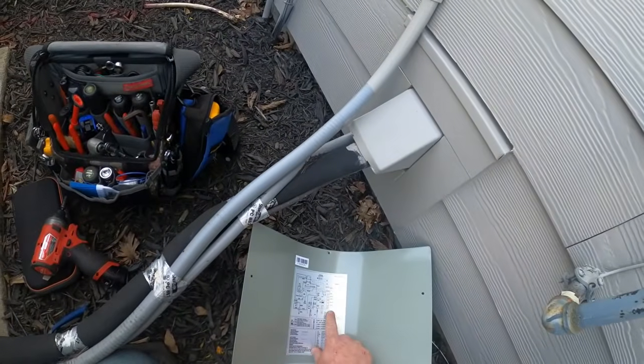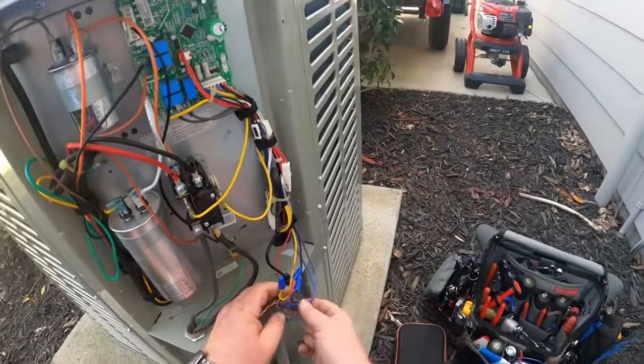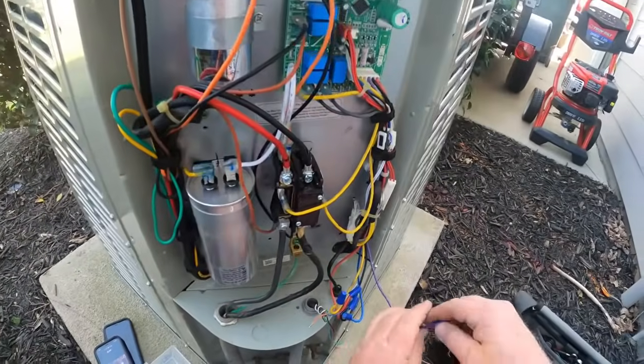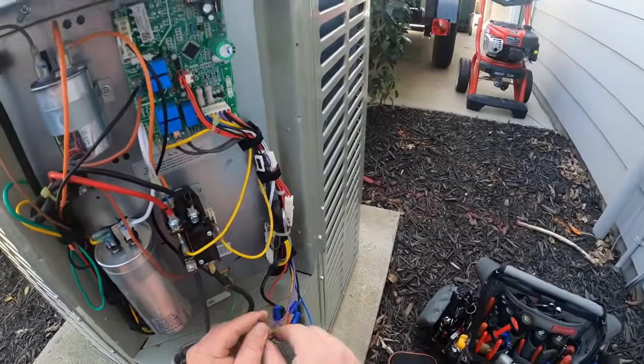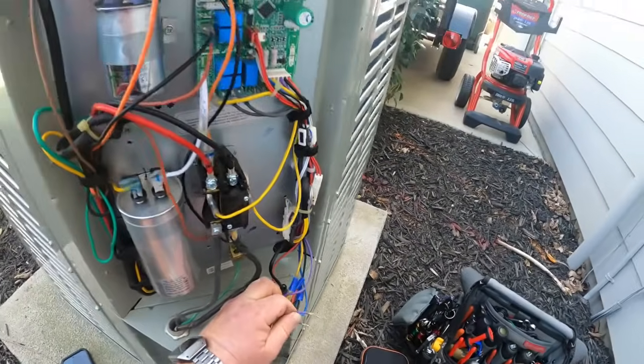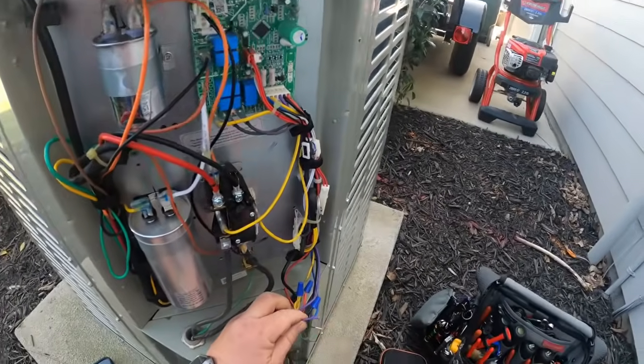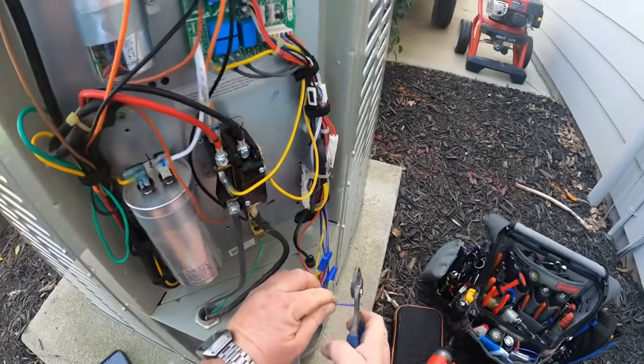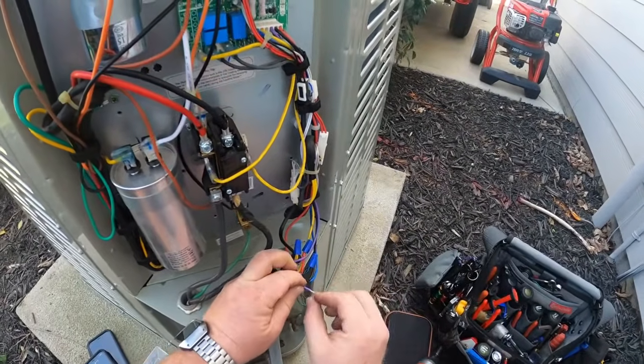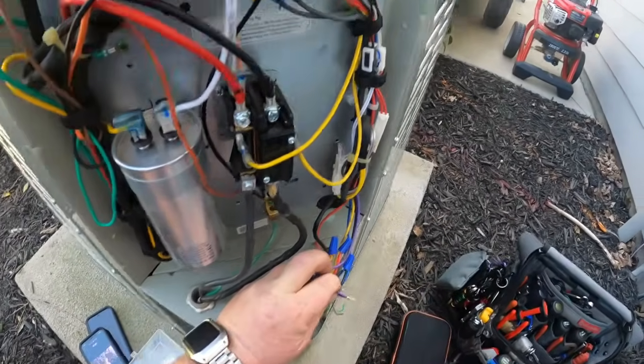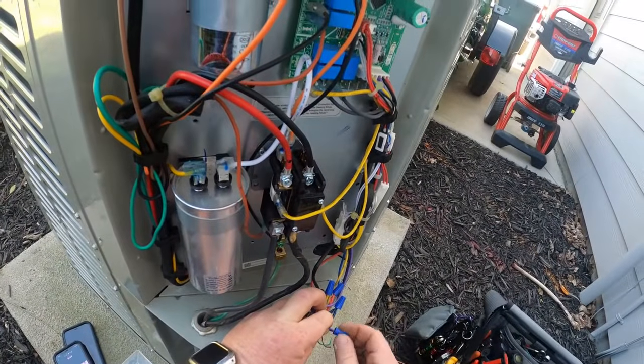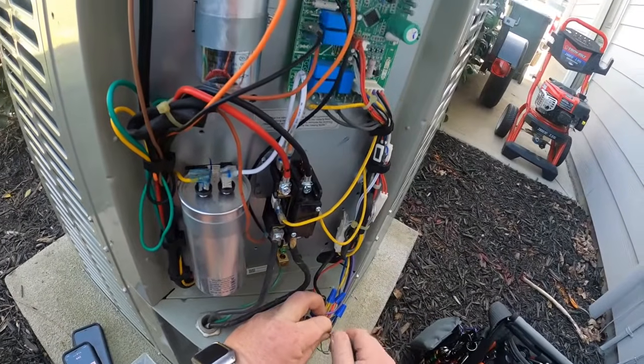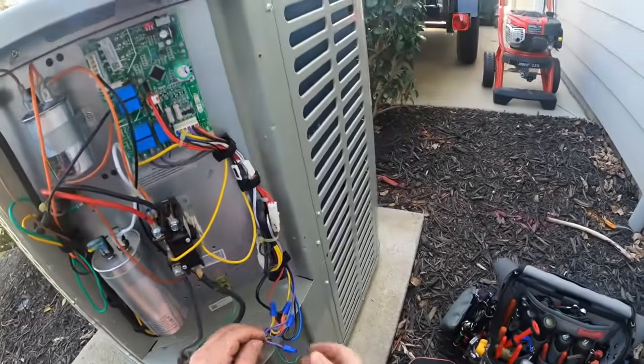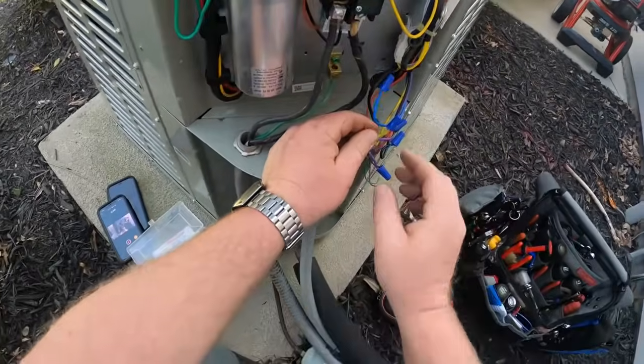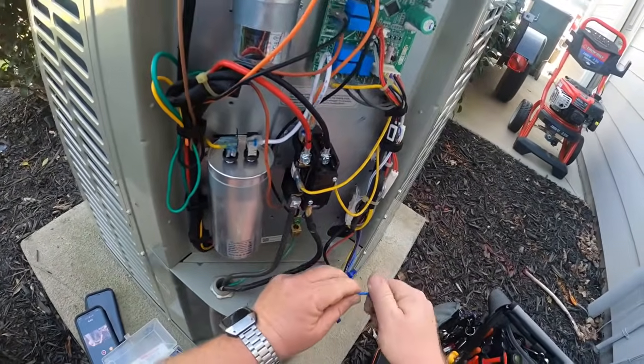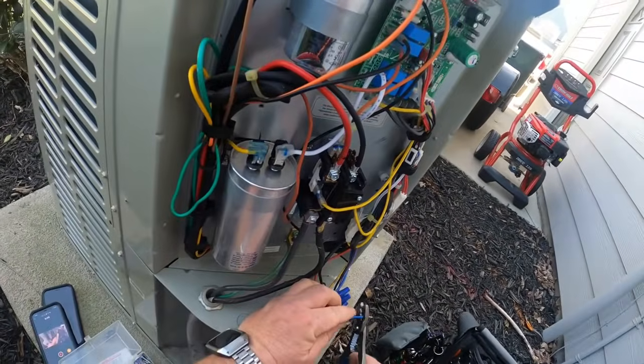So now our blue and purple, our purple is going to be our auxiliary. There's one that's here. It's going to be our auxiliary going back in, and we're going to tie that in to our black. So when it goes in defrost, this will go back into that board. That board will cycle on that furnace while it's running in defrost mode to cancel out that cold air. And then obviously we now have our blue for our reversing valve for heat.